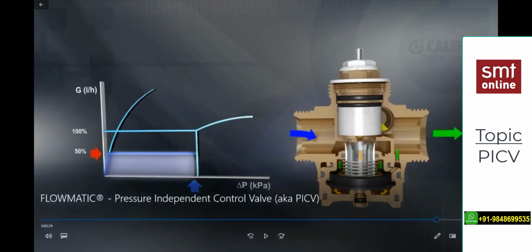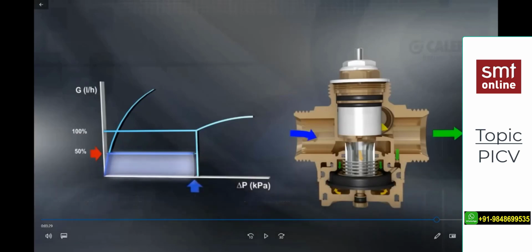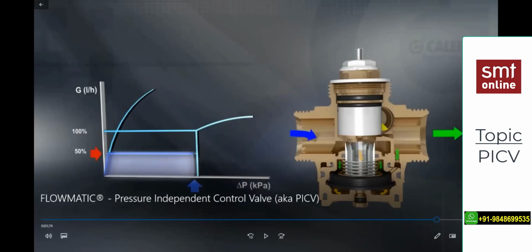For example, initially we balance this for the required flow. So when you switch on the unit, it will run at full load. And as the temperature is maintained in the space, the actuator will slowly push this valve down, and you see that the pressure increases on this side. So the excess pressure is used to push the spring. It also helps avoid hammering, or not exactly hammering; the excess pressure is going to be used to push the spring.